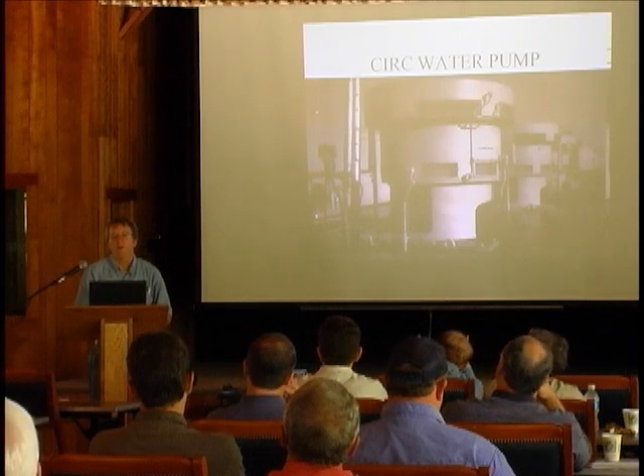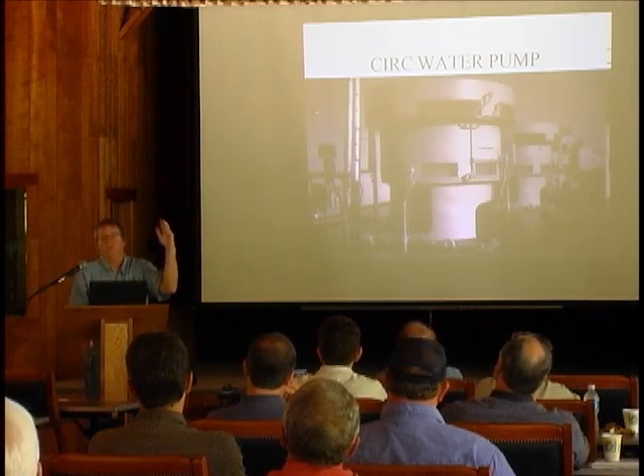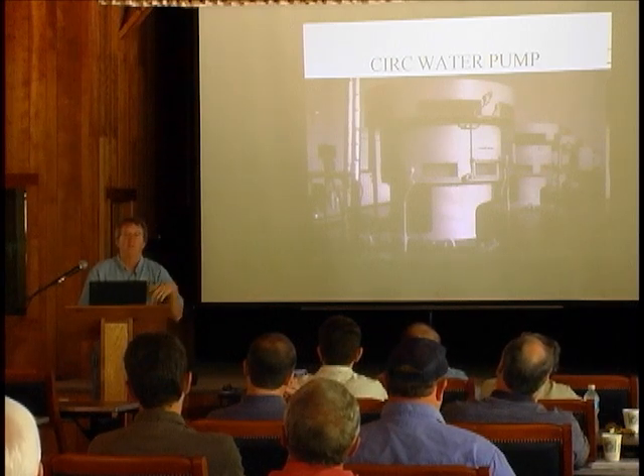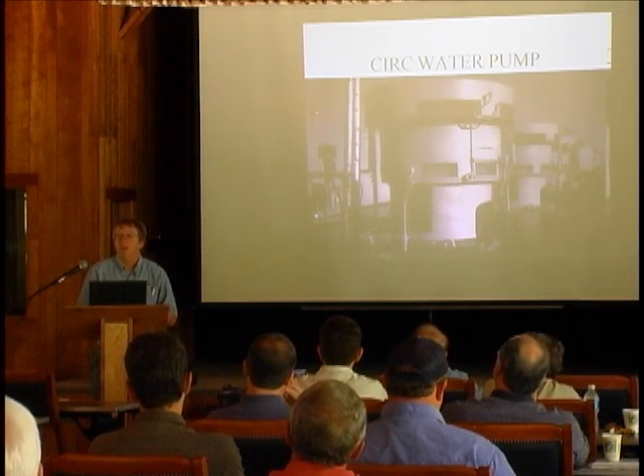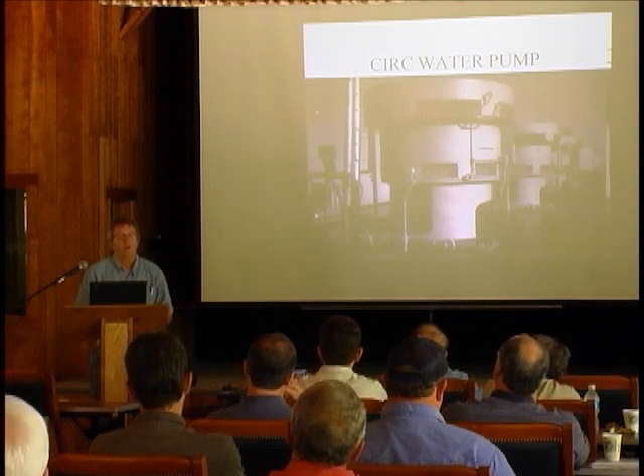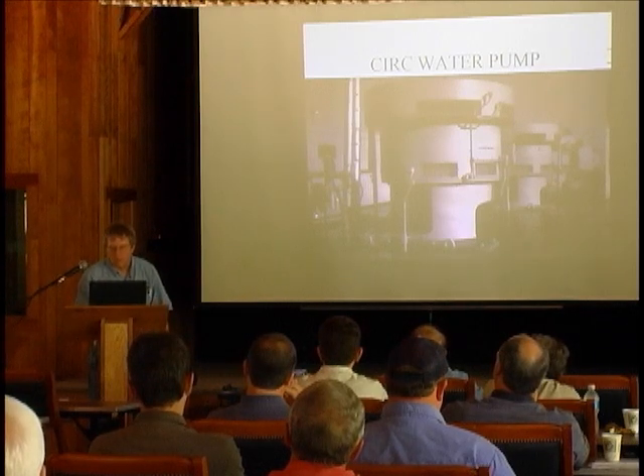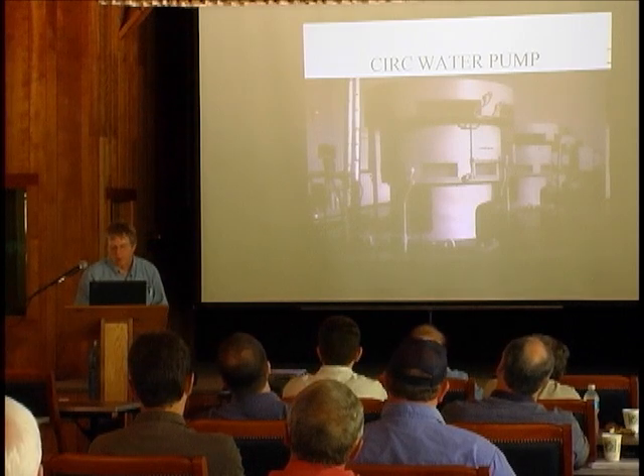And if you have too low a pressure, the flow comes up this way, and you get backside erosion on your volutes and your diffusers, and you end up with runout conditions. So anyway, that's just a basic primer on pumps. But that's why you're getting in trouble. And if you're doing vibration, you need to know where you're at on your pump head curve.